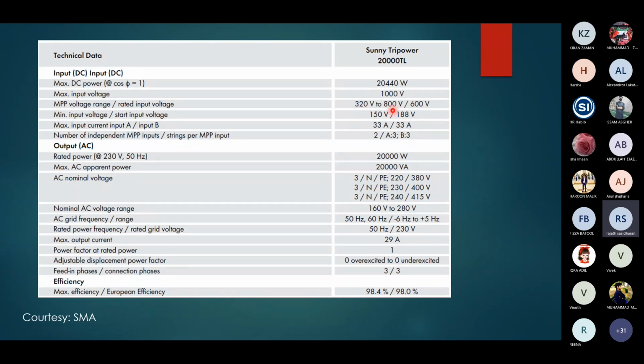So why is the MPP range lesser than the open circuit voltage? It's because once the panels are short circuited, it starts giving out current, and of course the voltage goes lower. But it should not go lower than 320 because of the conversion circuit. It requires a certain threshold to work, and then it gives you the maximum input current.